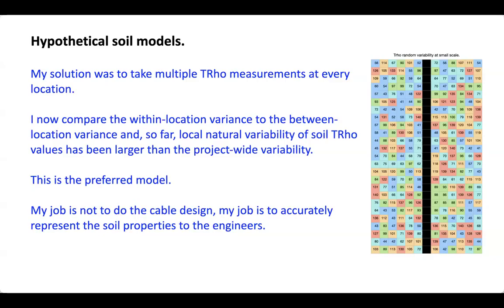I guess my online audience can't see me pointing at the screen, but if you pick any spot along here, it's pretty unlikely that there's more than 2 or 3 squares of the same color, which is telling you that there's such a high variability along that line that oversampling is the best antidote to not knowing what's going on. And the statistics have told me conclusively that this is probably the better model for the thermal distribution in the project area, and that they should frankly design for the average thermal property, not the low or the high. But that's not up to me because I don't do the cable design. Everybody has risk aversion at different levels, so you have to design accordingly.